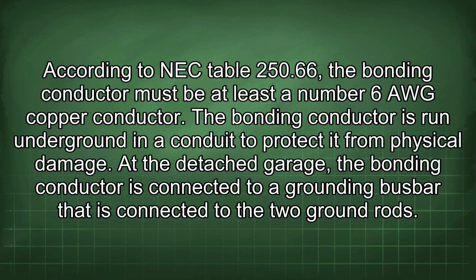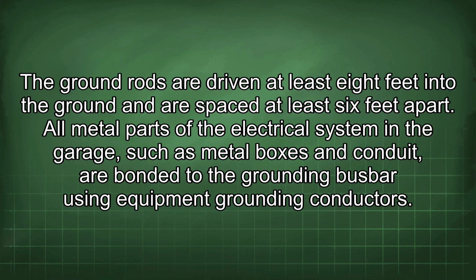At the detached garage, the bonding conductor is connected to a grounding busbar that is connected to the 2 ground rods. The ground rods are driven at least 8 feet into the ground and are spaced at least 6 feet apart. All metal parts of the electrical system in the garage, such as metal boxes and conduit, are bonded to the grounding bus by using equipment grounding conductors.